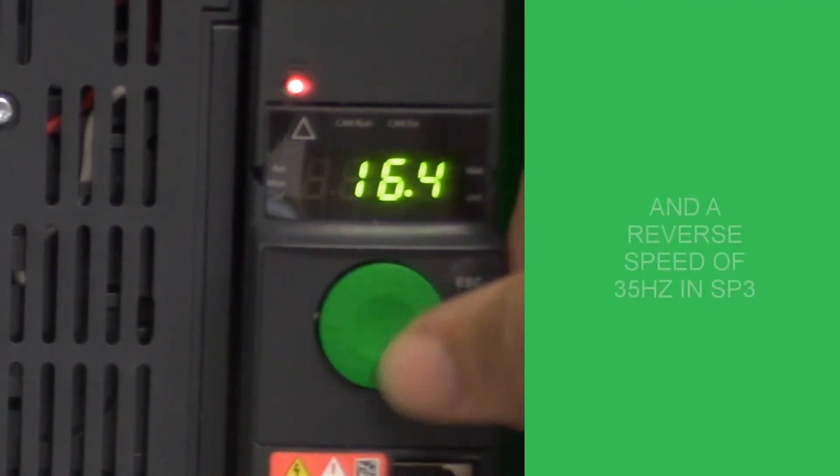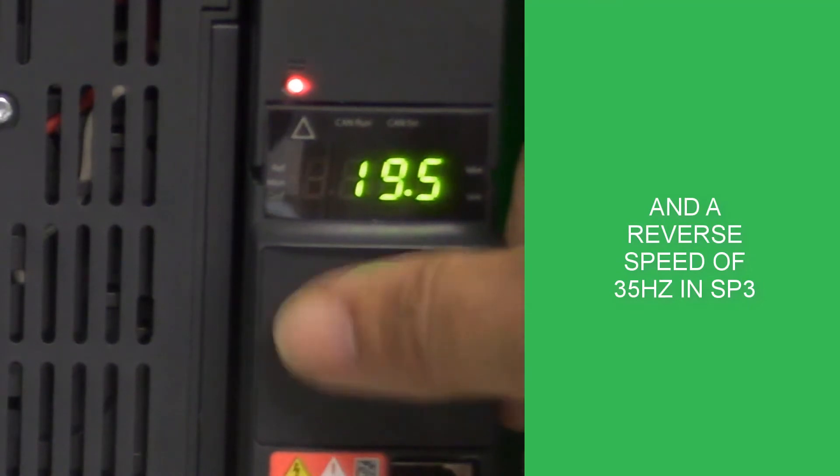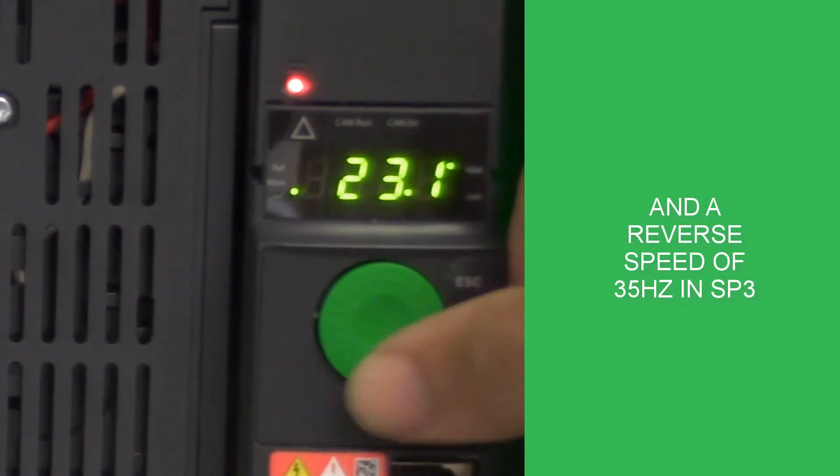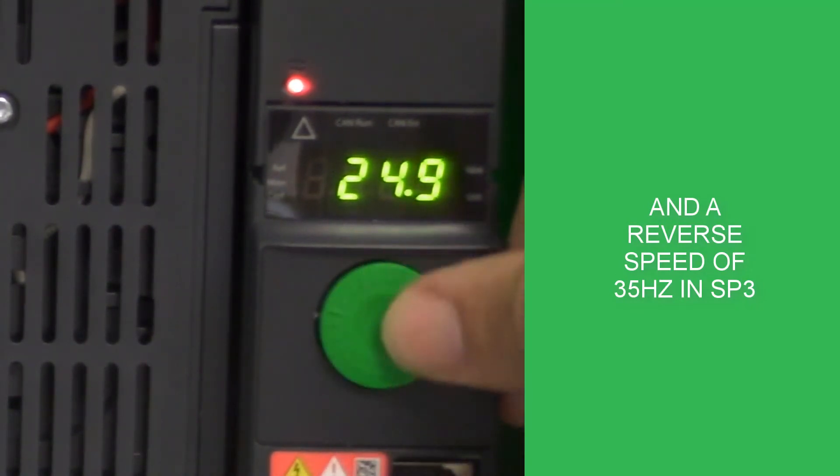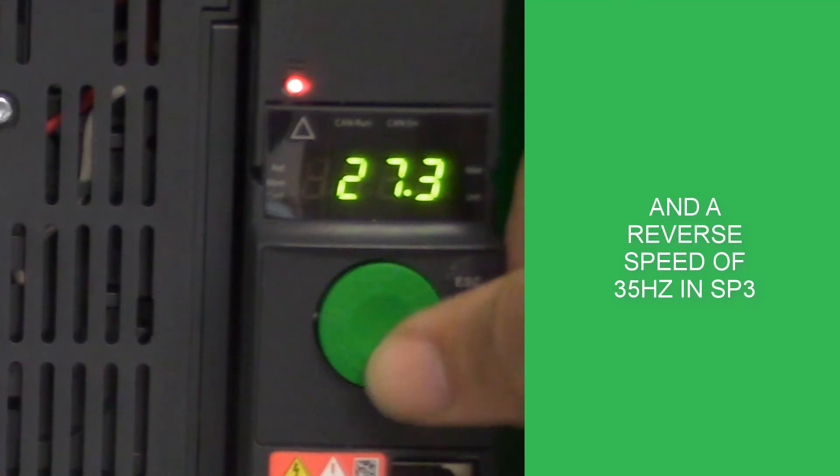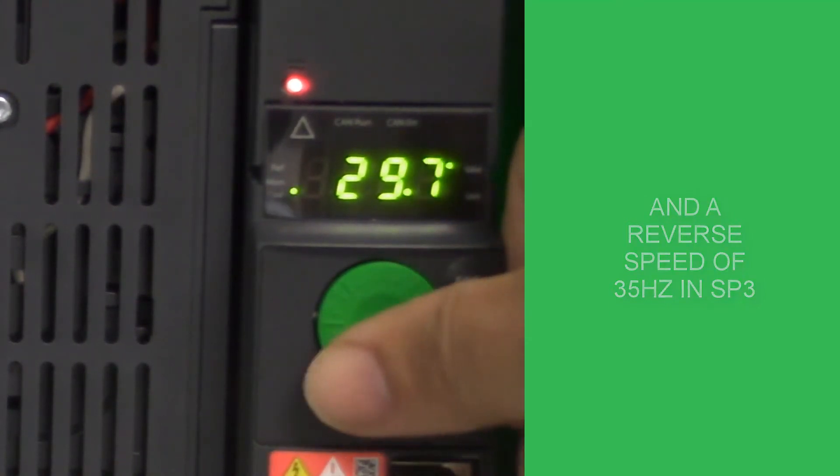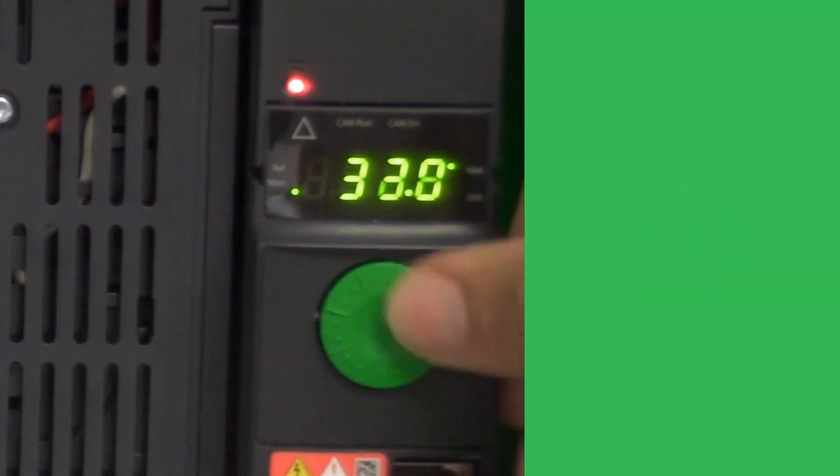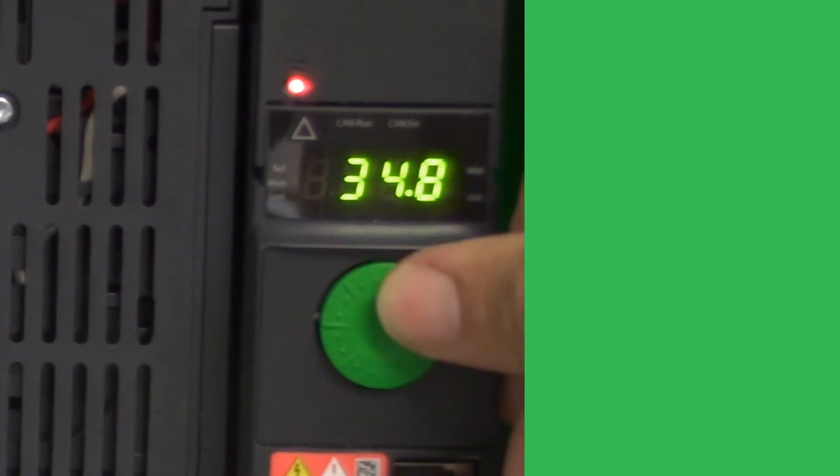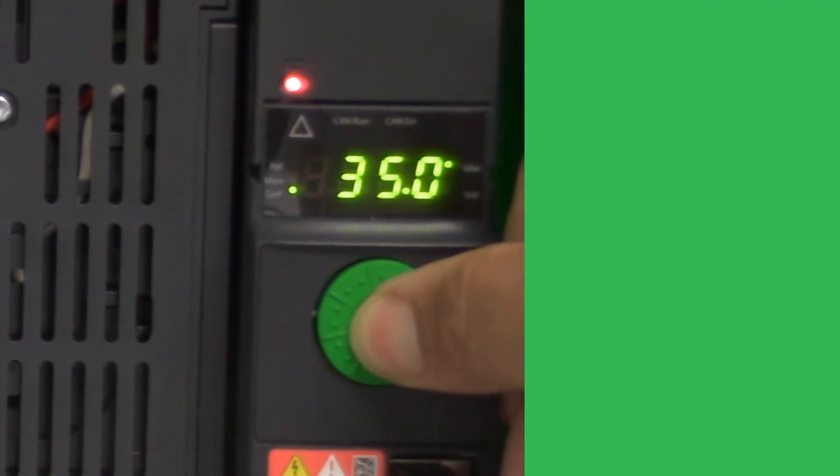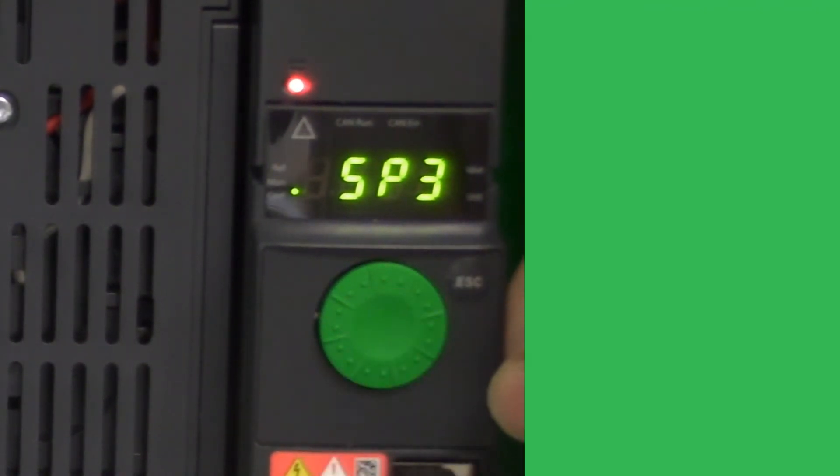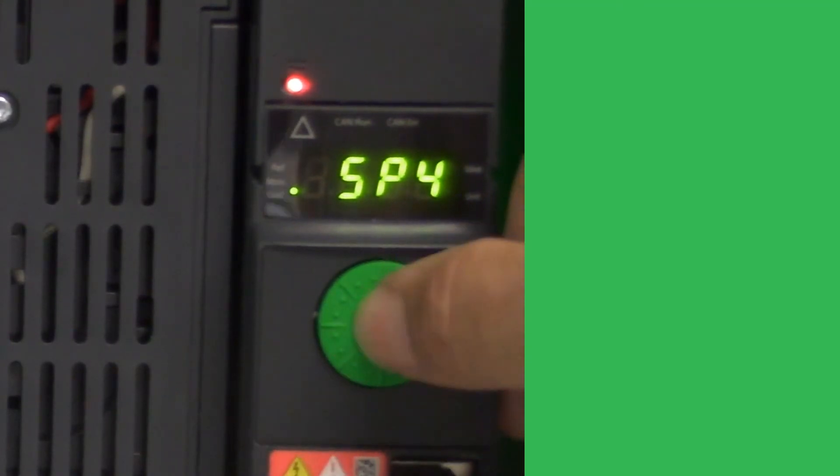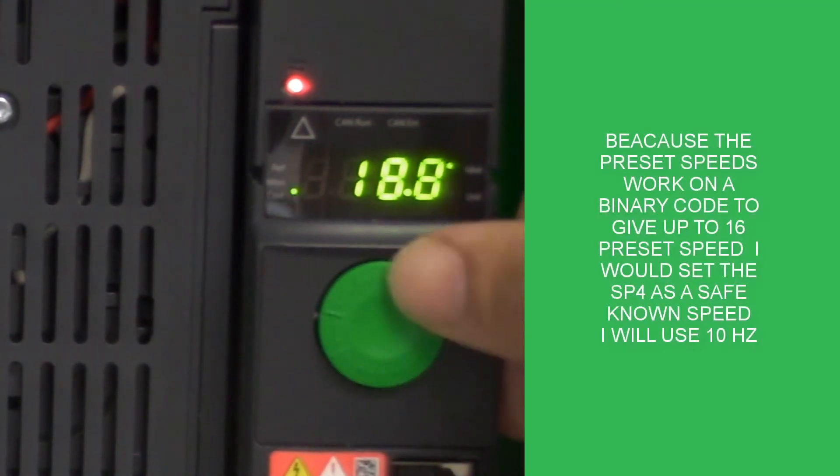One thing to remember is that on these two inputs, it's a binary coded input. So if both come on together, they will assign the speed set in preset speed 4. For reasons of safety, I would usually assign this to a slower speed or zero speed to suit the application, but something that would point out that there is a problem with the system.